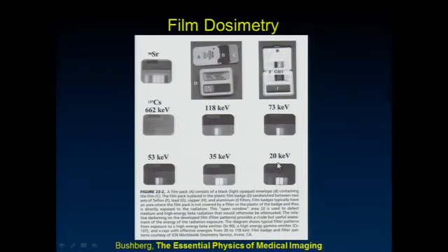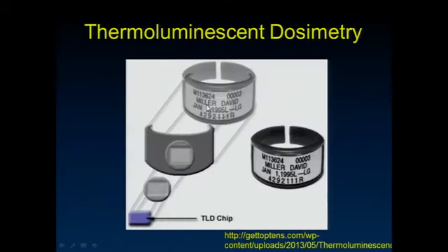And so you notice you've got this variation in exposure on the surface of that. At low energy, some of that metal had really great stopping power for those low energy X-rays. And as you got higher up, notice that they didn't have very good stopping power at all. So by looking at the variation of exposure, you could get a rough idea of what the average energy of radiation exposure was. And then by looking at overall, globally, how exposed this piece of film was, you can get an idea of the total amount of that particular type of exposure.